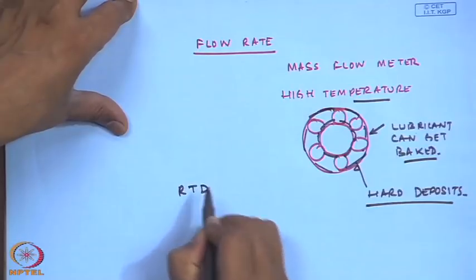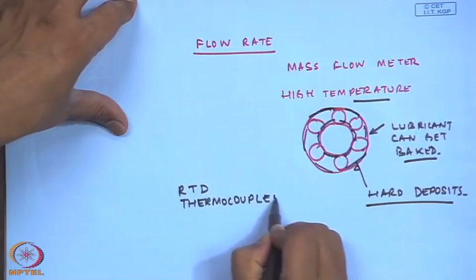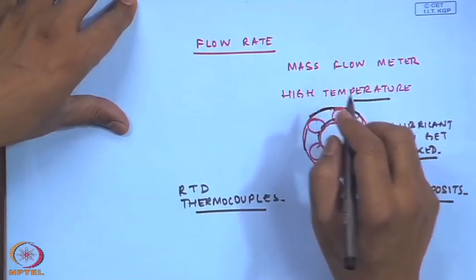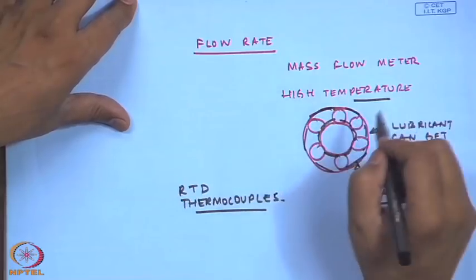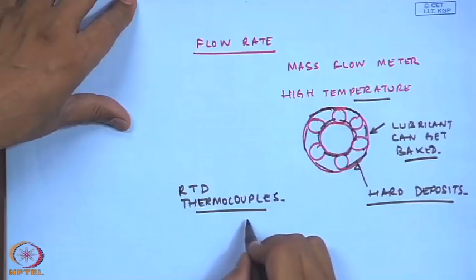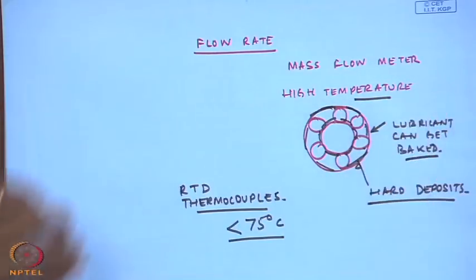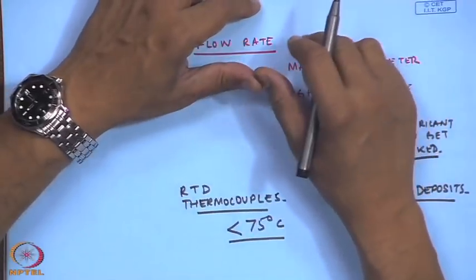Temperatures in compressors must always be monitored using RTDs (resistance temperature detectors) or permanently mounted thermocouples. In the machinery maintenance unit, bearing temperatures of compressors are regularly monitored. The recommended industry principle is to maintain bearing temperatures below 75 degrees Celsius. To maintain such a temperature, RTDs and thermocouples are installed around the bearings of fans, compressors, and blowers.